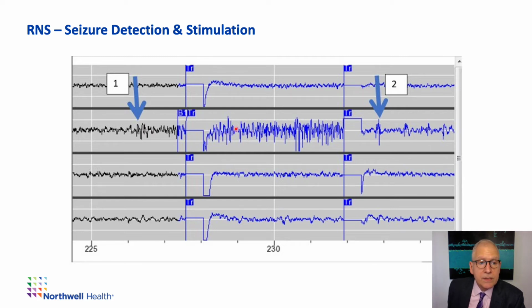And in this case, you can see that the seizure discharge continued. And so the device detects that and it delivers a second stimulation. And in this case, you can see that the seizure discharge has now changed. It's gone into a termination pattern and the seizure's over. So the device has aborted the seizure. That's the idea behind the operation of this device. It's constantly sampling the brain activity. When it detects a seizure, it delivers a pulse of current to terminate the seizure at its origin.